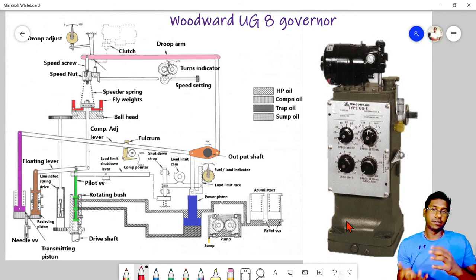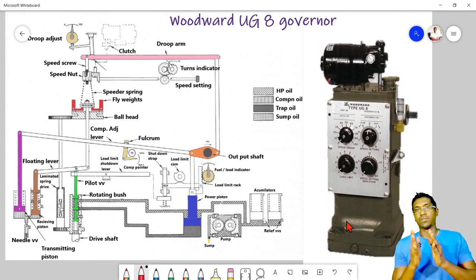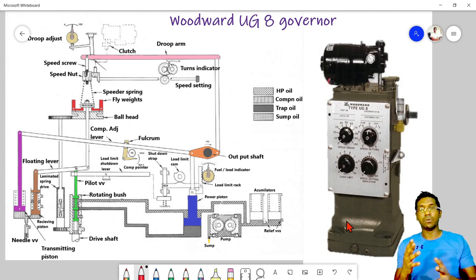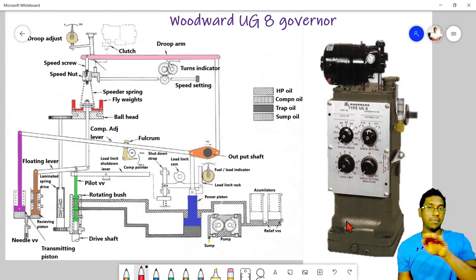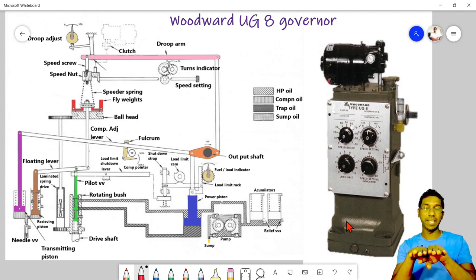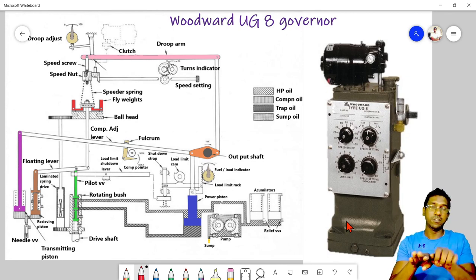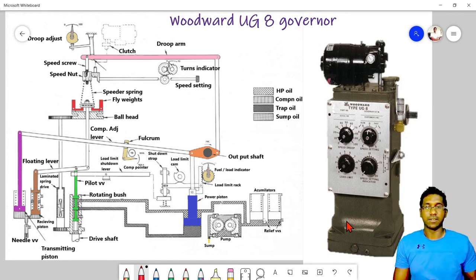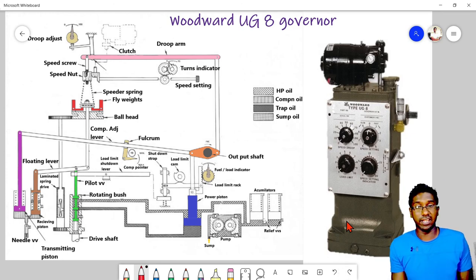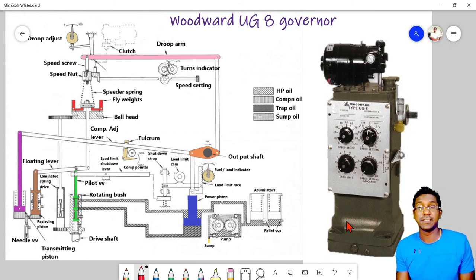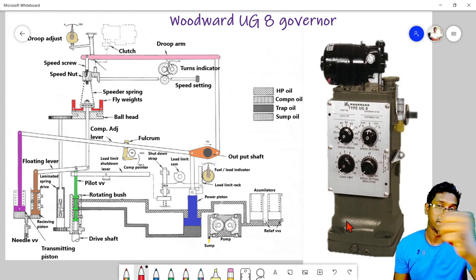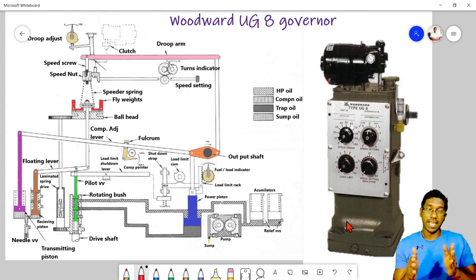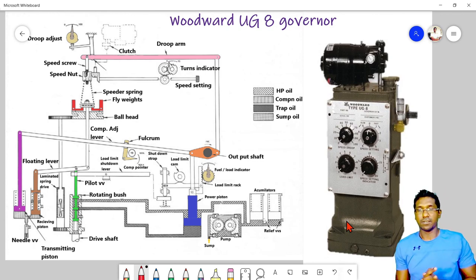After setting the pointer to maximum upward position, loosen the compensation needle valve until there is considerable hunting in engine speed — leave it for a minimum of 30 seconds to remove air from the hydraulic system. Then begin closing the needle valve until stable operation is achieved. Once settled at a stable RPM, close the needle valve one quarter turn more — that is the compensation adjustment. If stabilization cannot be achieved by adjusting the needle valve alone, refer to the manual for additional steps to vary the compensation rate before needle valve throttling.